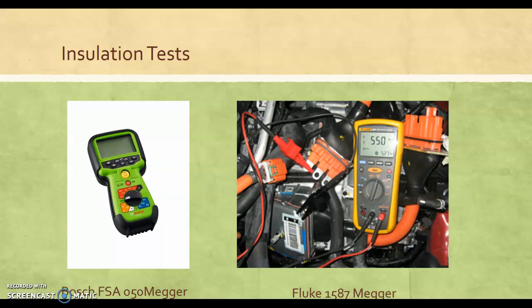It gives you a sweeping motion, which you'll see in the video at the end of this canvas. And then of course the Fluke 1587 we had at class. Fluke makes a great meter. I love my Fluke 88 that I had, but this particular meter is kind of a catch-all. It does the insulation testing. It does voltage and ohm reading, but its ammeter is limited to milliamps.